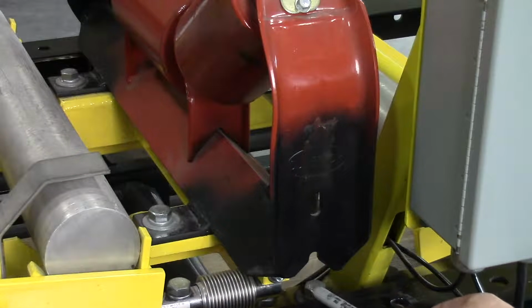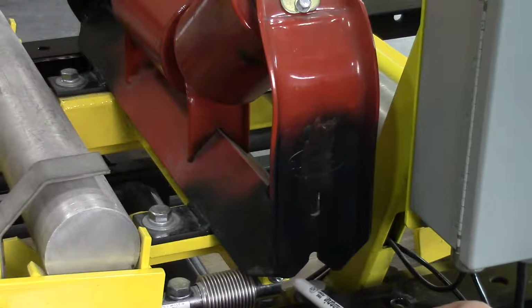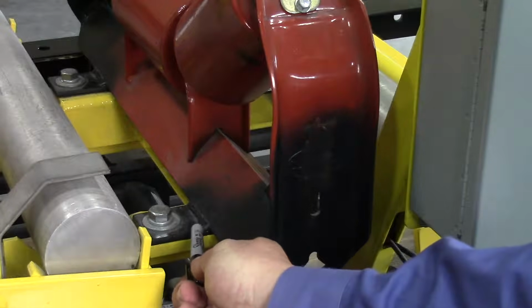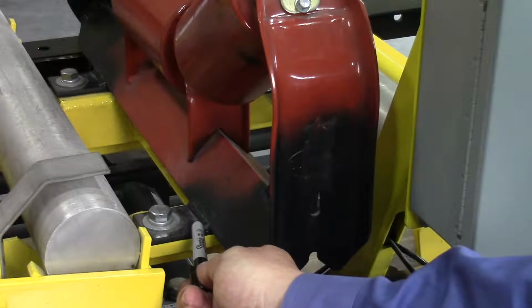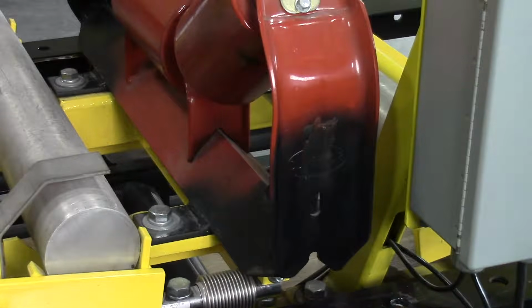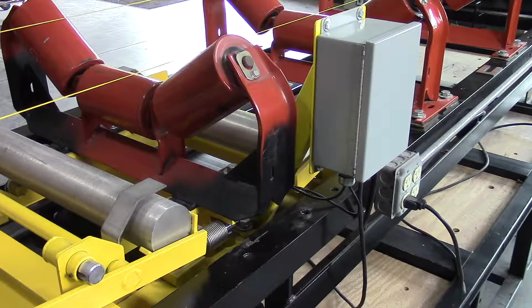The idler is centered on the belt scale and marked. Usually this is while the belt scale is sitting on the ground. It's just easier to work with at that time. The unpainted scale mounting brackets are removed and then welded to the idler after marking the appropriate location. You can see here the scale mounted to the brackets and the supports in place. Ideally, you don't want to weld it while it's sitting on the scale or close to the load cells unless you really know what you're doing, because you can destroy the load cells.